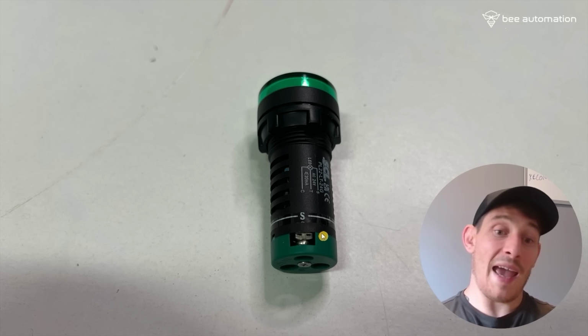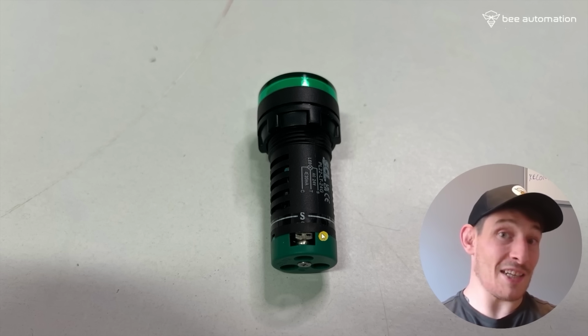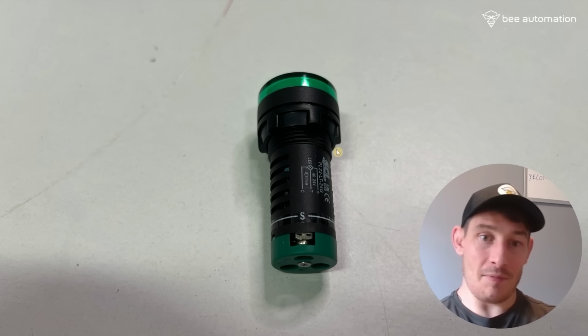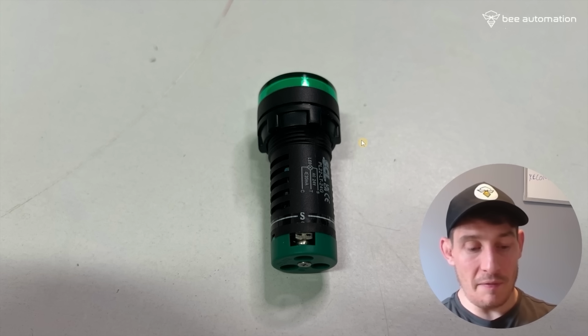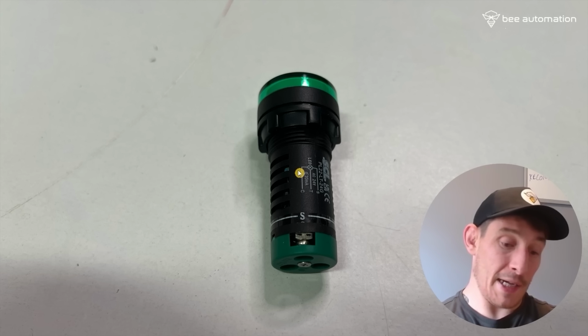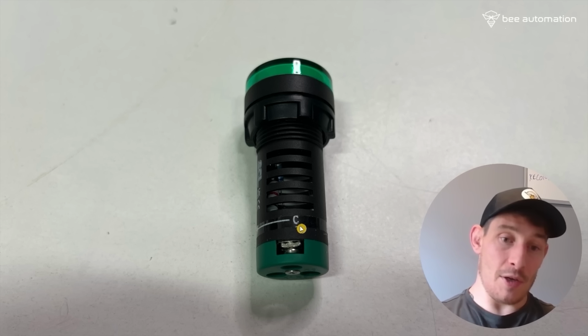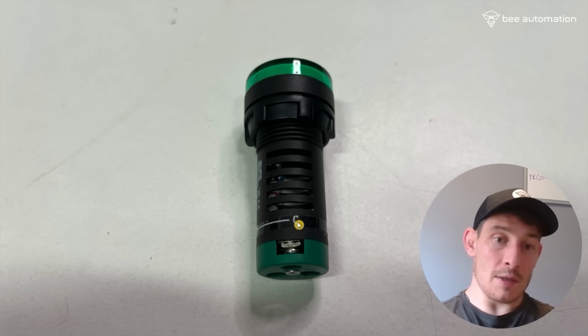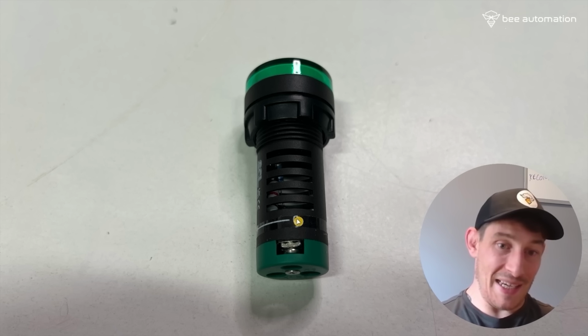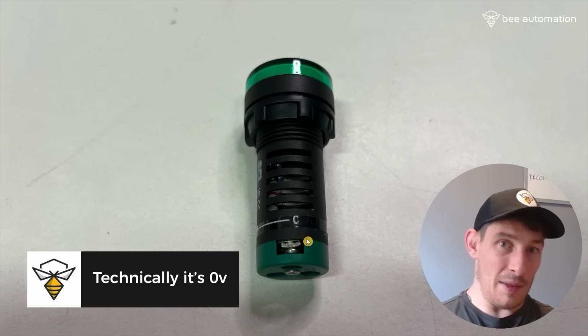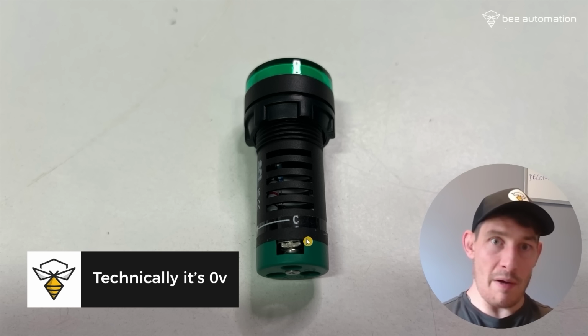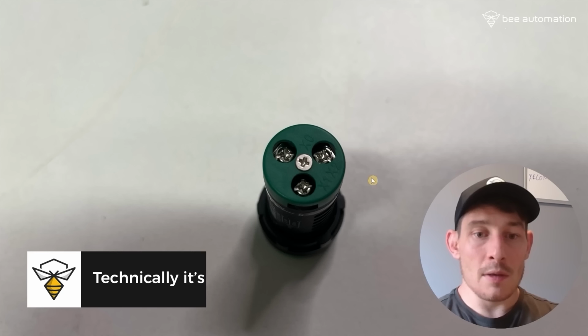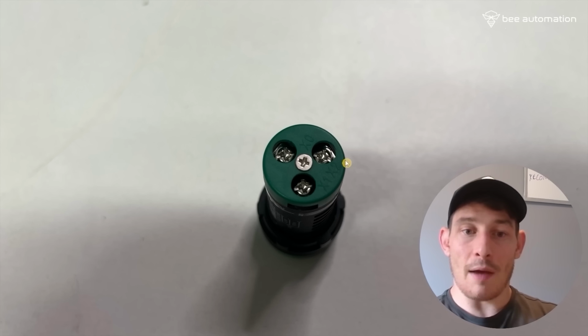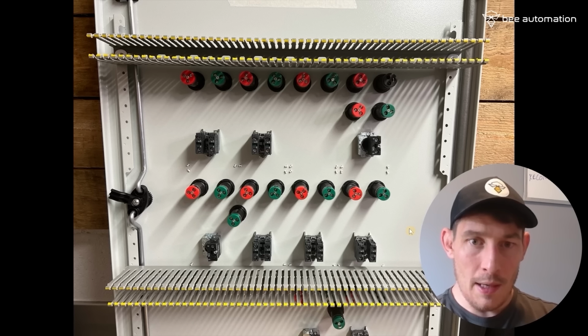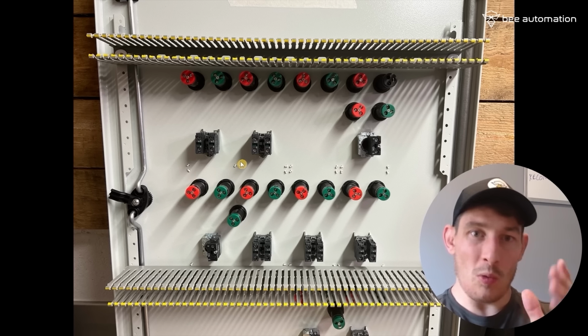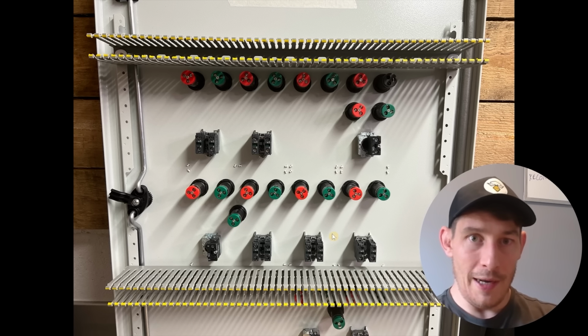We've got the S terminal, the signal terminal, to indicate if it's running or in fault, and that'll be coming from a relay. Then you've got the C terminal, which is common. Because these are 24 volt AC indicator lights, that'll be the neutral or 0 volts, however you want to refer to it. So here's another shot of the 3 terminals, and I'll make sure they're all in the correct position before tightening them all up.